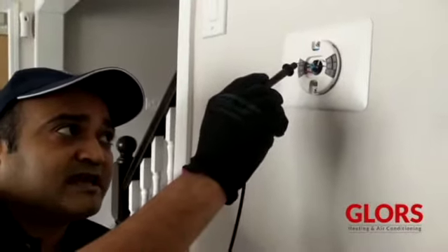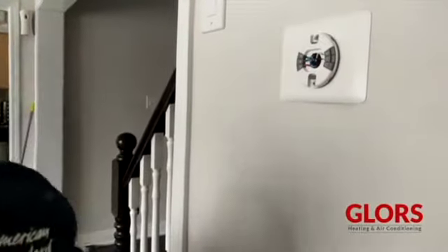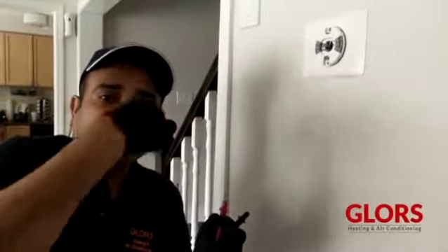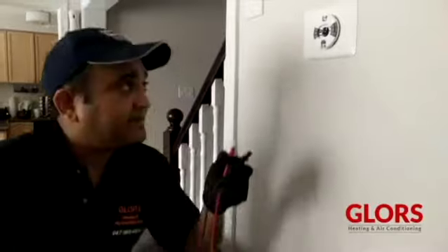So this has to be energized when you set the thermostat, and once it's energized, this power goes back to the furnace, and then from the furnace to the AC. But here it's not going back into the furnace after you set the thermostat. So I believe that's a thermostat issue. We will advise the customer accordingly and let you know if it's something else.